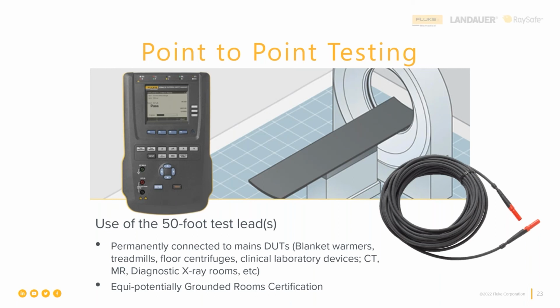And it's a valid way to do tests for permanently connected to mains devices like blanket warmers, treadmills, floor centrifuges, clinical laboratory devices, any X-ray system, and the like. So point-to-point testing, and we provide the longer test leads so you can get the job done.